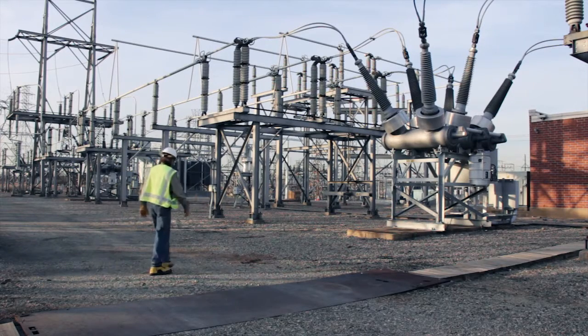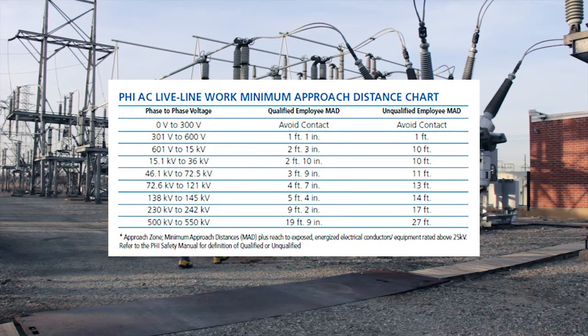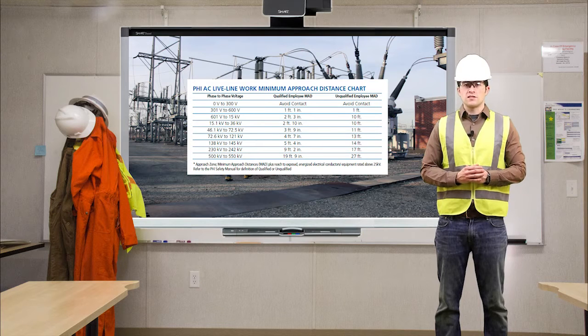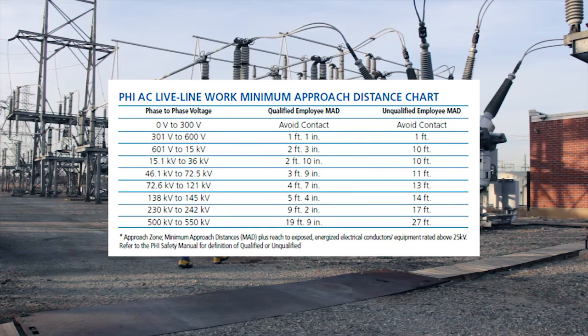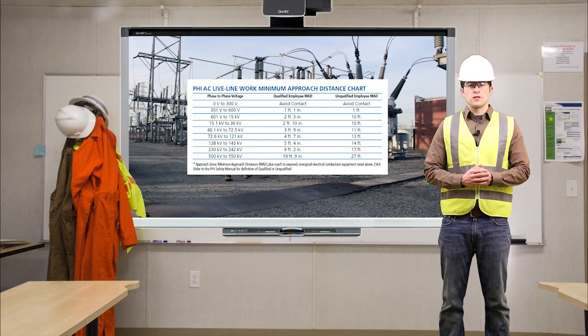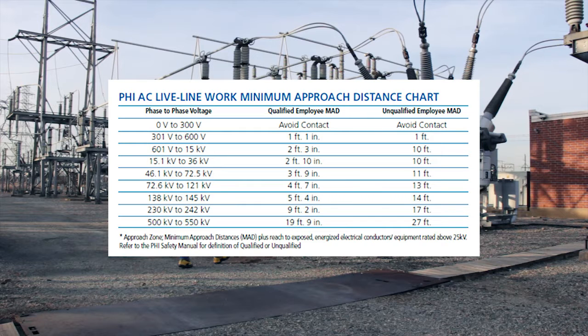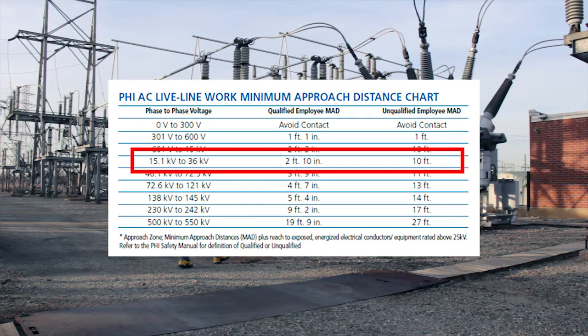Finally, a qualified worker should maintain the minimum approach distances, or MAD, corresponding to the voltages for which they will be exposed. MAD is defined as the closest distance a worker is permitted to approach an energized object. There is a specific MAD depending on the voltage of the energized object as defined in the minimum approach distance chart. After determining the nominal voltage, the corresponding MAD must be maintained. For example, let's say you have a crew working in the vicinity of a 25 kilovolt circuit breaker. According to the chart, the minimum approach distance for a qualified individual is 2 feet 10 inches plus a standard reach of 31 inches.